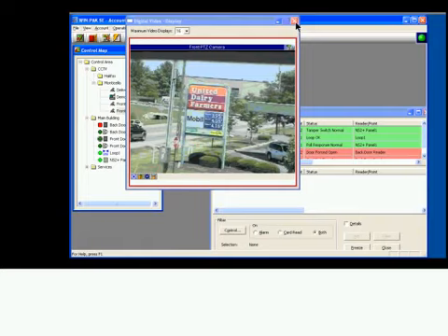Any other Winpak questions regarding video integration? This is Adam again. I've been thinking about those presets again. What if you were to set preset 1 at a particular position through Winpak, but an operator configuring the DVR set preset 1 in the DVR at a different position? Which one of those takes precedence? The most recent configuration? Yeah, whoever made the last change. Based on that, you can change your rights in Winpak software so that they can modify it, and the same thing on the DVR. So an operator can lock down the DVR as well as Winpak. Okay. Good question, thanks.